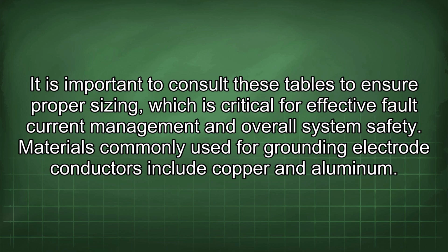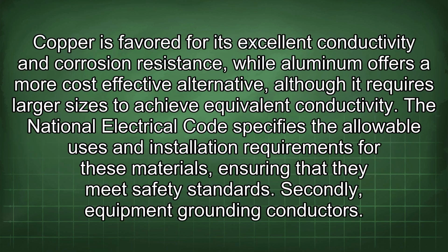Materials commonly used for grounding electrode conductors include copper and aluminum. Copper is favored for its excellent conductivity and corrosion resistance, while aluminum offers a more cost-effective alternative, although it requires larger sizes to achieve equivalent conductivity. The National Electrical Code specifies the allowable uses and installation requirements for these materials, ensuring that they meet safety standards.